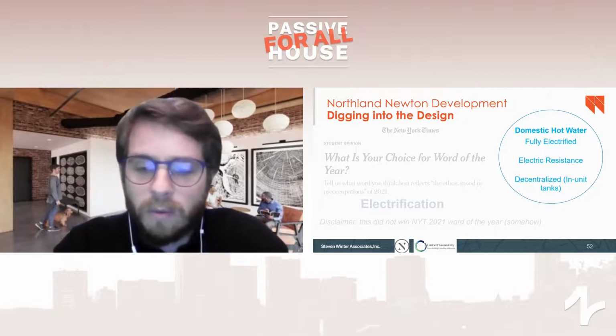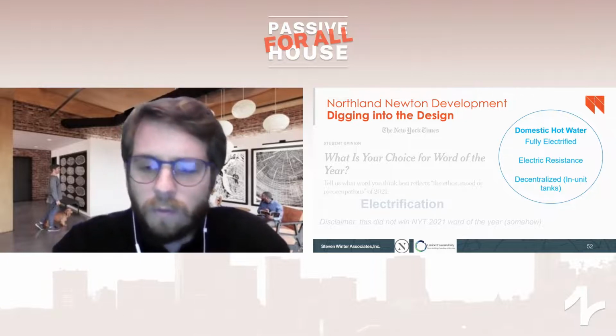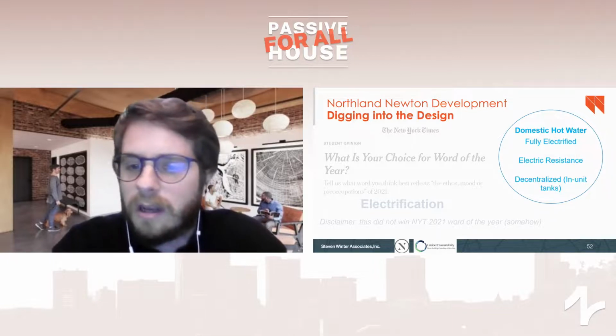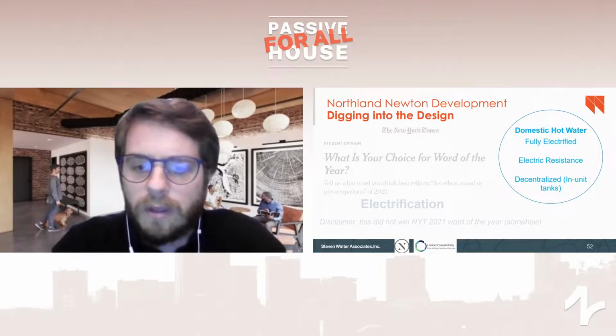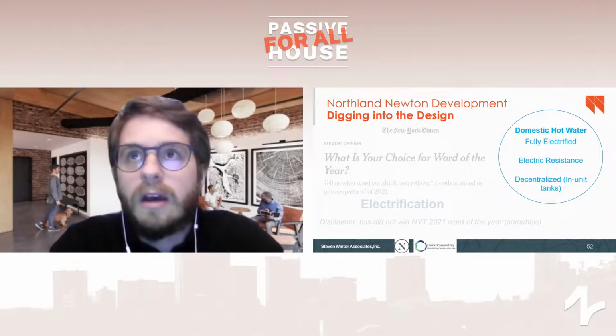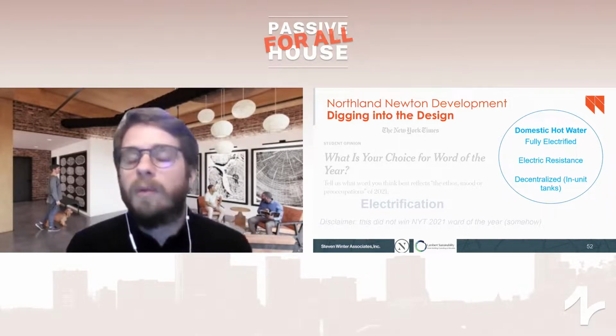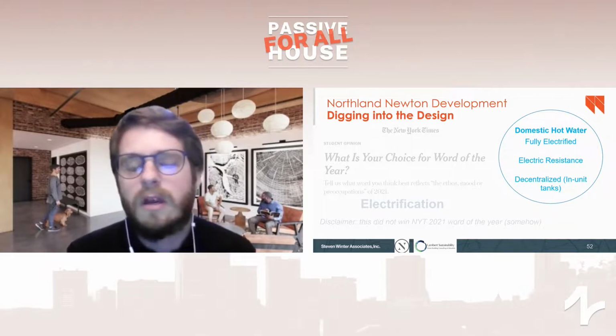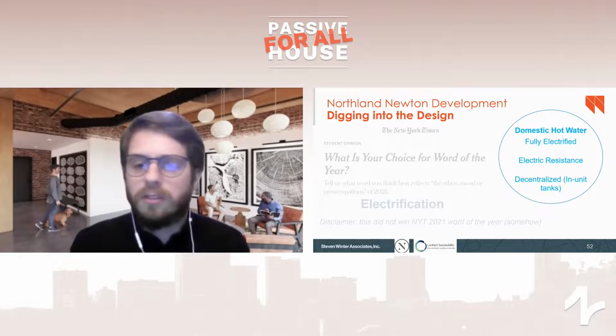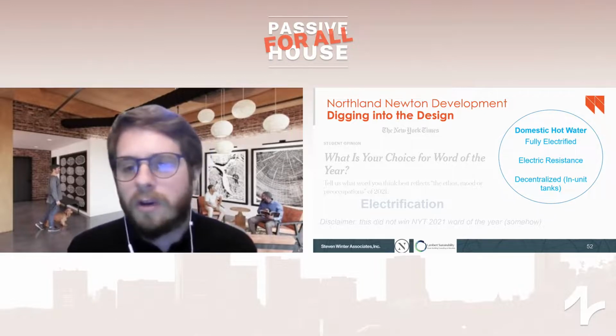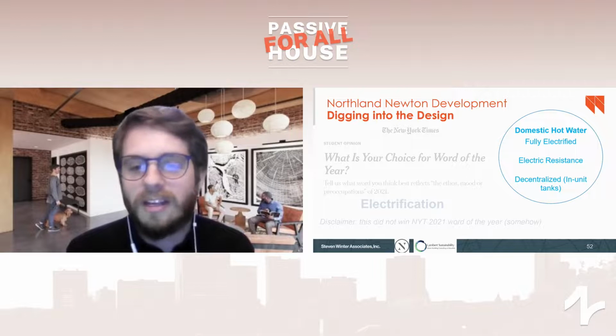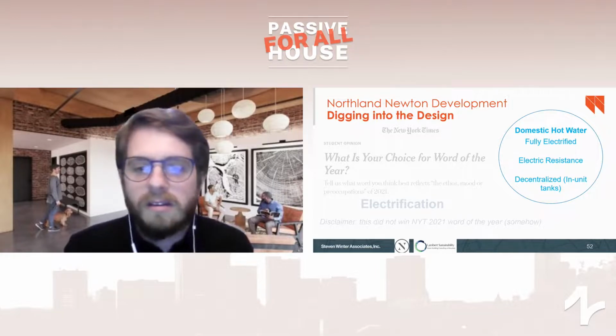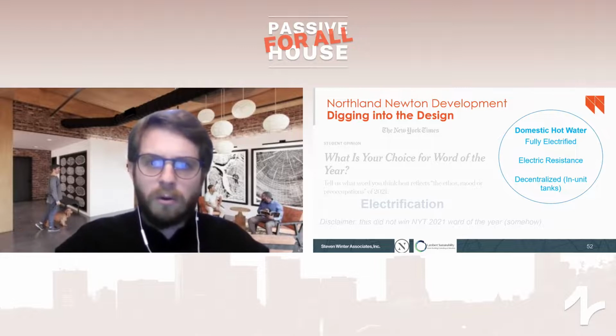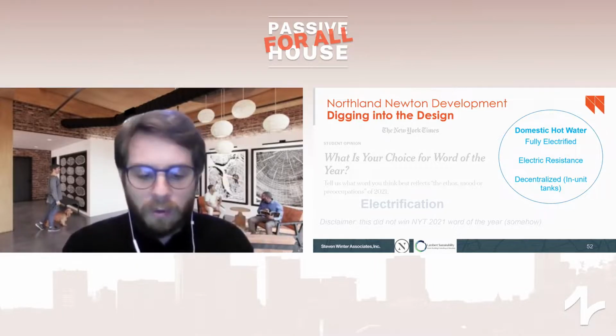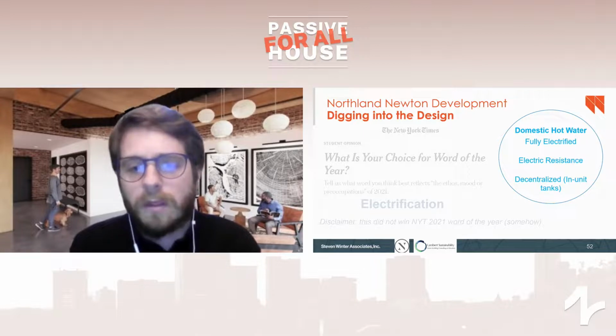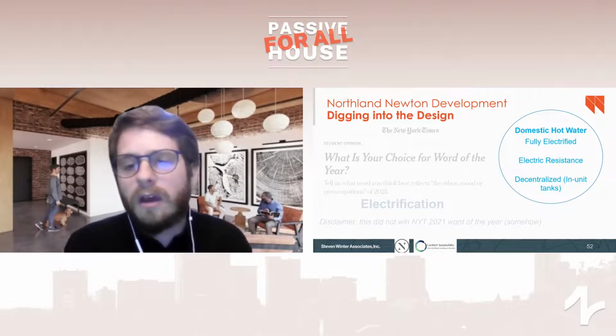So really the options that we looked at were heat pump water heating options, particularly some case studies that we've seen where heat pump water heaters are installed in multifamily buildings with just a decentralized approach, like in-unit heat pump water heaters. And it's really, really challenging to get those to work properly. They need enough air volume. They're going to be blowing out cold air. They're noisy.